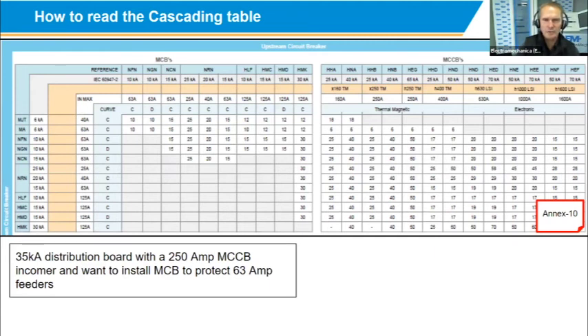So how do we read a cascading table? Again, Annexure 10 in the back of the electromechanical catalog is the table for cascading. So you've got a 35 kA rated distribution board with the 250 amp moulded case circuit breaker as incomer, and you want to install miniature circuit breakers to protect the 63 amp feeders going out of the board, maybe to a sub-distribution board, or you can even install 20 amp miniature circuit breakers to protect plugs and light circuits. So you look for a 250 amp main incomer that's rated 35 kA.